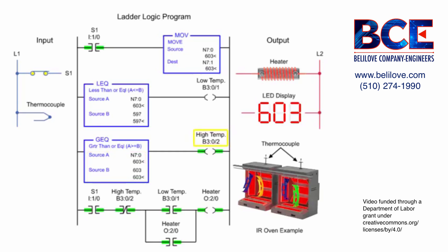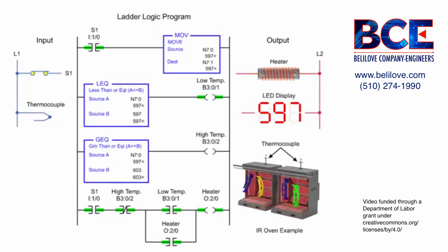When the high temp output is true, the heater turns off and remains off until the temperature reaches 597 degrees or lower. The cycle is repeated to maintain the average set point temperature of the oven at 600 degrees Fahrenheit.